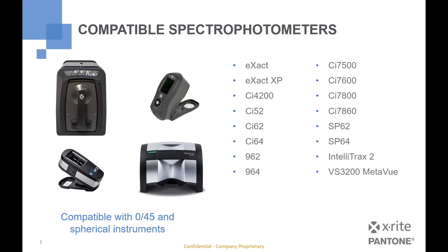So, what devices work with NetProfiler? NetProfiler is compatible with 0/45 and 45/0 spectrophotometers as well as all spherical spectrophotometers — whether that is the benchtop spherical instruments, the handheld spheres, or some of the handheld and benchtop 0/45s. Most or all are supported with this product line to help bring these back and improve how these devices measure over time.